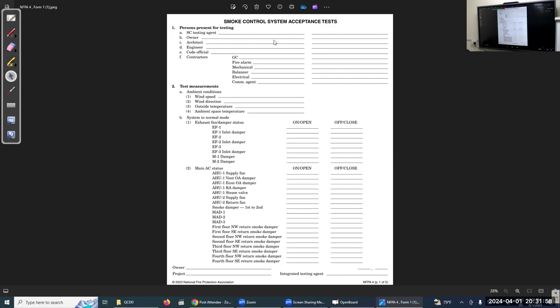So it will tell you who conducted the test and who is in which team. As we discussed, these are all the ITA teams, the integrated testing agents. It has the general contractor, fire alarm, mechanical systems, balancer, electrical, and commissioning agent. All these persons have to be there and they have to sign. Then they will check the ambient conditions: whether the exhaust fan is working, opening and closing, how the pressure is being maintained, how the pressure valve and stairwell pressurization systems work, and how the ventilation works. All the stuff they will check.